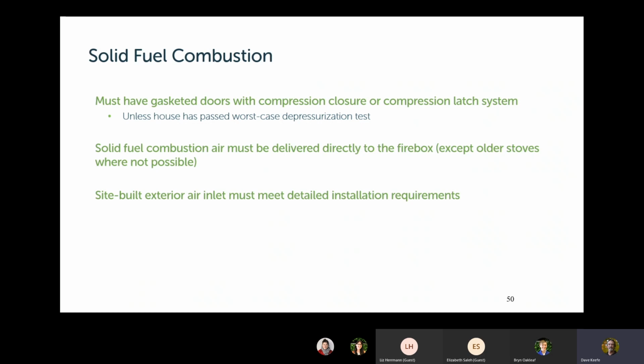If you're building something on site, like a site-built fireplace, you also have to provide combustion air, and you have to follow the installation requirements that are in the code. So even though I haven't put those details in here, in the code itself, it has detailed installation requirements for site-built air inlets, including how big they need to be, where they need to be located, what kind of materials they need to be built out of, that sort of thing.